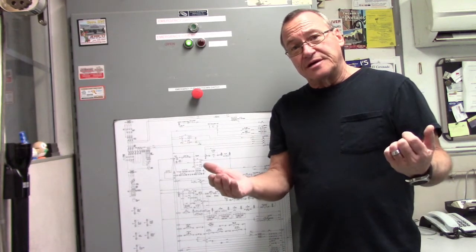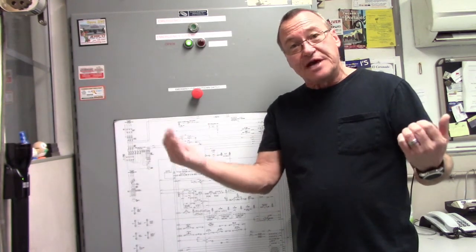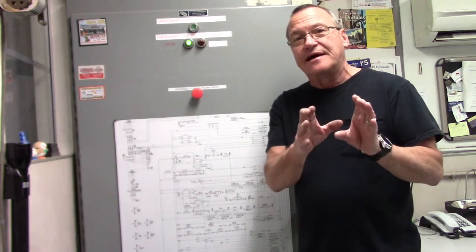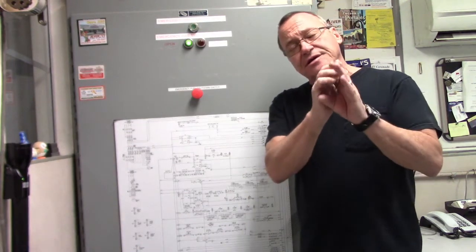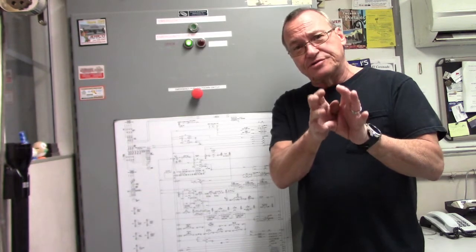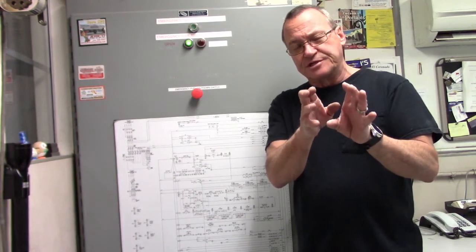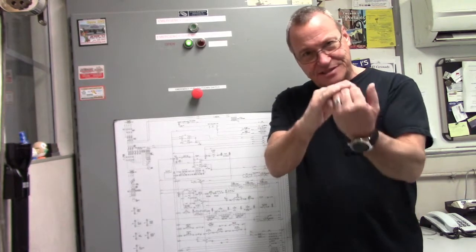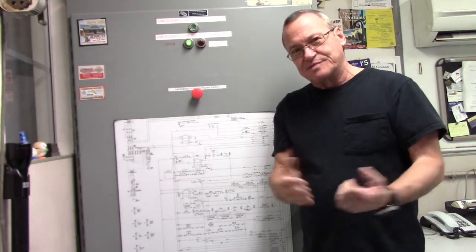If we had looked at the components and two of the switches were made, the only other one is the purge air switch, and we can't see that. So then I would have to look at that component on its own and do some troubleshooting of the purge air switch. But in this instance, you can visibly see the switch wasn't made, which was pretty easy.